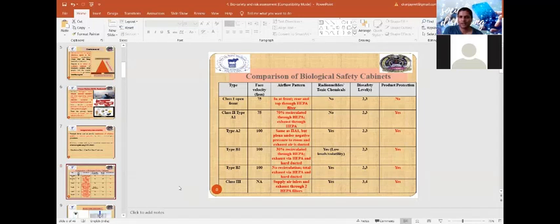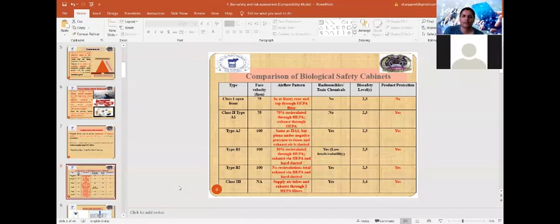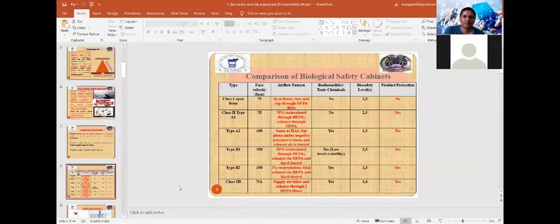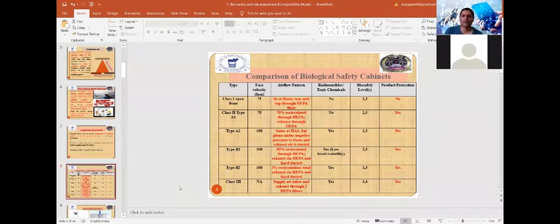Type B1 again has 100 fpm face velocity, but only 30% of the air inside the cabinet is recirculated through HEPA filters, and exhaust air also goes through HEPA filters with hard ducted permanent structure. It may be used in BSL-2 or BSL-3 laboratories. Type B2 has no facility for recirculation — all air entering the cabinet is exhausted through HEPA filters via a hard duct.